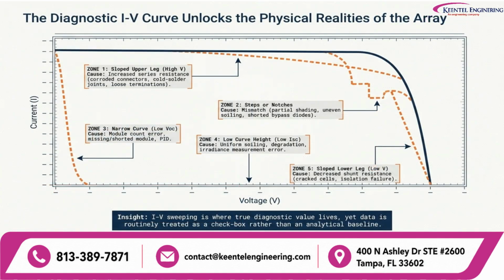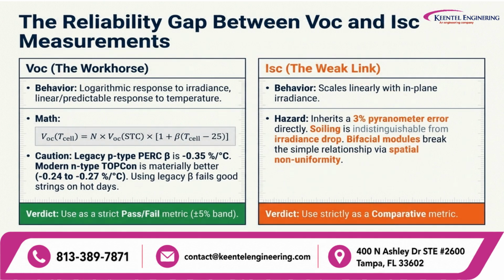Current voltage curve tracing is far more than a checkbox commissioning deliverable. It is a full physical diagnostic of your array. Deviations in specific regions pinpoint exact failure modes. A sloped upper leg reveals elevated series resistance from loose terminations or bad solder joints. Notches and steps indicate bypass diode failures or module mismatch. A narrow curve signals missing modules or potential induced degradation. Reduced curve height exposes soiling or pyranometer calibration errors, and a sloped lower leg warns of compromised shunt resistance and cracked cells.